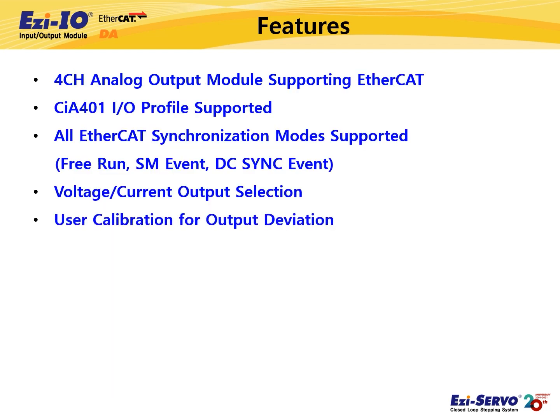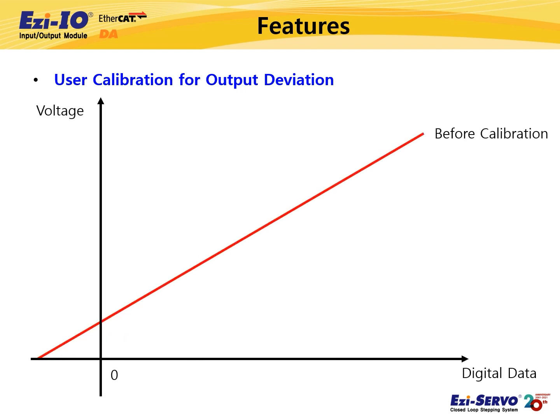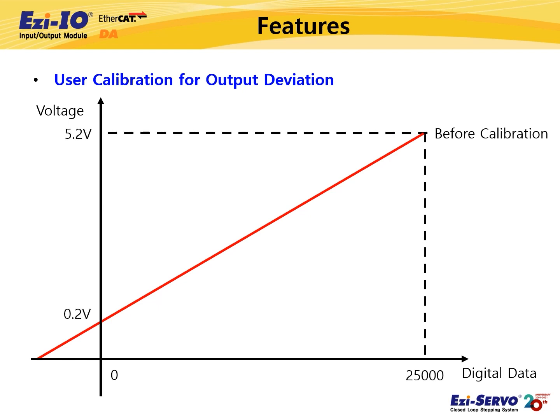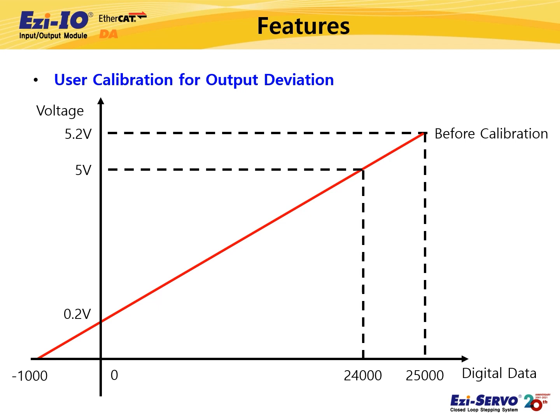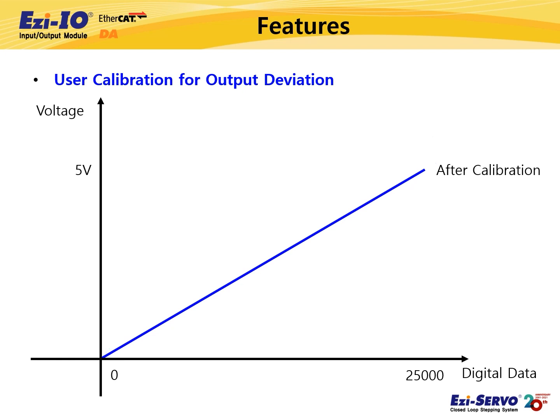Easy IO EtherCAT-DA provides an output deviation calibration function. Deviation in output signals can occur due to various conditions such as connected devices, cables, and connection methods. Easy IO EtherCAT-DA can reduce this deviation through the calibration function. For example, when the output range is 0 to 5 volts, a digital value between 0 and 25,000 should be converted to 0 to 5 volts. However, due to deviation, if the output is 0.2 volts at digital value 0 and 5.2 volts at digital value 25,000, you can set the calibration function's low value to minus 1,000 and high value to 24,000 so that the actual output is 0 to 5 volts when the digital input is in the range of 0 to 25,000.